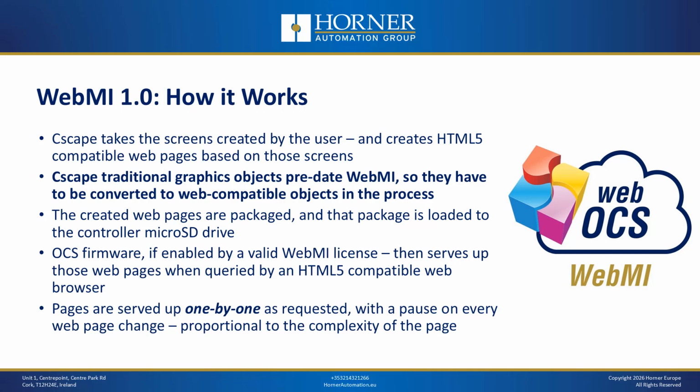The resulting web pages are packaged and loaded onto the micro SD drive on your controller. OCS firmware, if enabled by a valid WebMI license, will then serve up those web pages when queried by a HTML5 compatible web browser. The serving up of these web pages is done one by one as requested, meaning there's a pause on every page change.